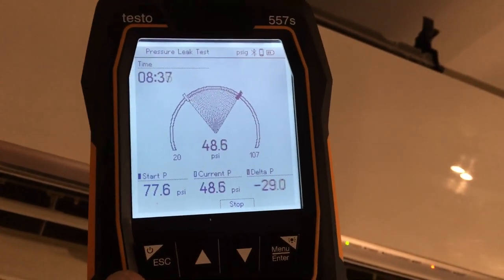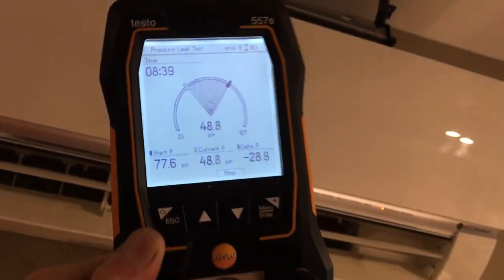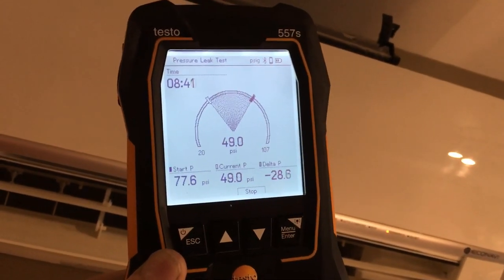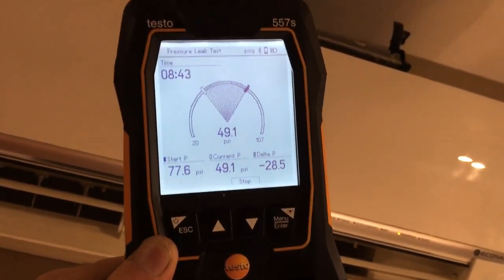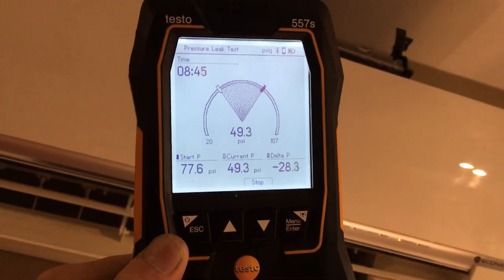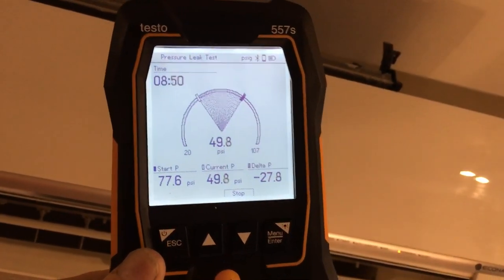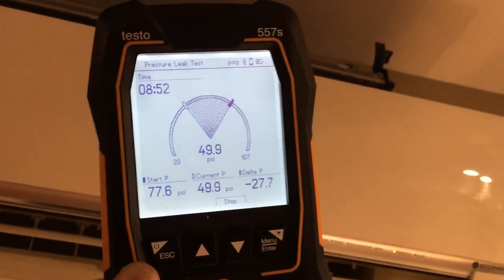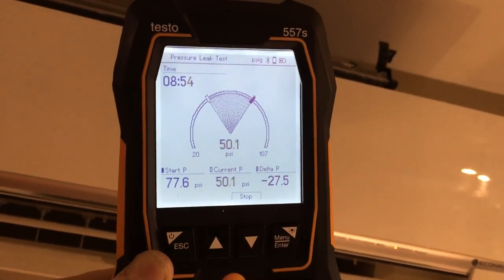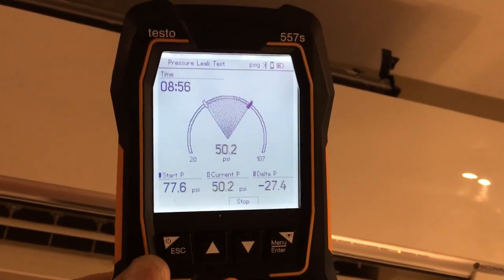And no, I'm not filling it up. So for you guys in automotive who like to think you could hook up a set of gauges and tell if the system is full or not, you could have a full system, you can have a half full system, or you could have one drop of liquid refrigerant and you would get the exact same pressure.